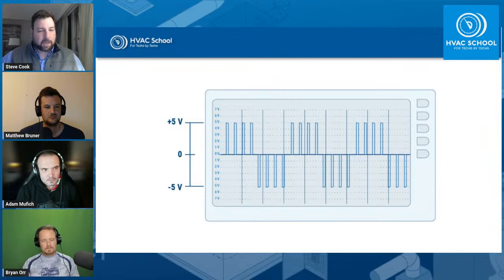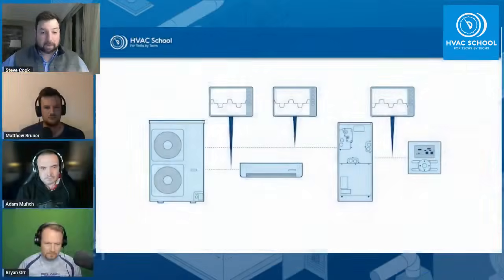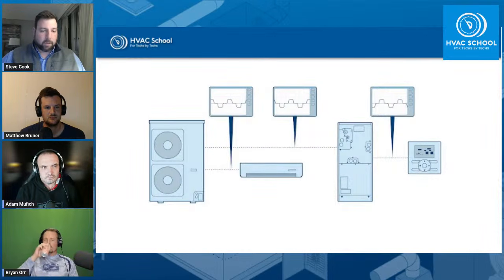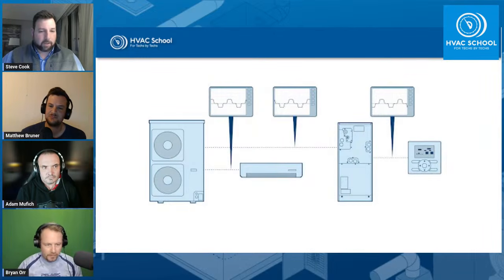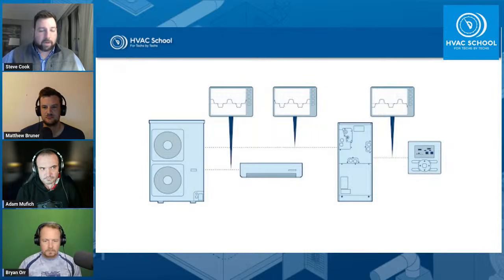So typically there's a starting place for that signal, and usually the starting place is the outdoor unit. For the most part, that signal derives from the outdoor unit, and it's carried throughout essentially the communication bus of the system. So if you were to remove the two communication cables off of an indoor unit, for example this air handler, it will not communicate with it at all. Now, if I just cut those lines, at the outdoor unit there will be voltage there. And depending on what sort of equipment it is, if it's never started and it doesn't ever see that air handler, you may never have a fault. But if that communication's cut and lost, and that outdoor unit says, hey, there's supposed to be something here and there's not, you will get a fault on that. But it depends kind of on the brand of equipment.